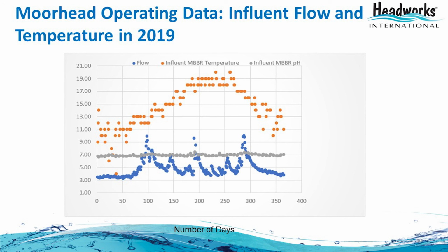This shows the variations in flow. Blue dots are the variations; you can see the x-axis is January 1st to December 31st. The first spike comes when the snow melts, around March. The second spike comes in the summer rain season. The third spike in the fall. So even with the tripling of the flow, we cannot wash out the biofilm. Activated sludge can be washed out.